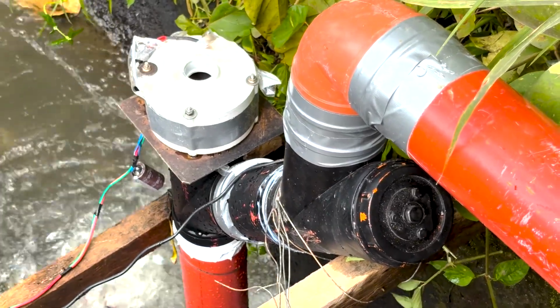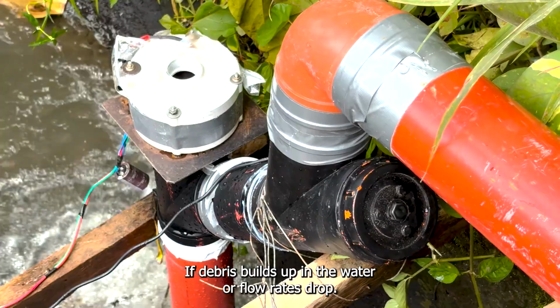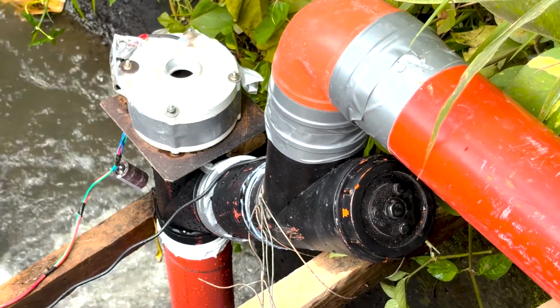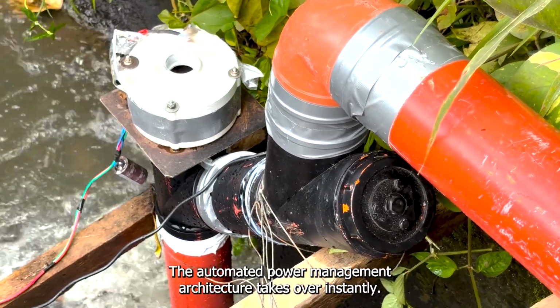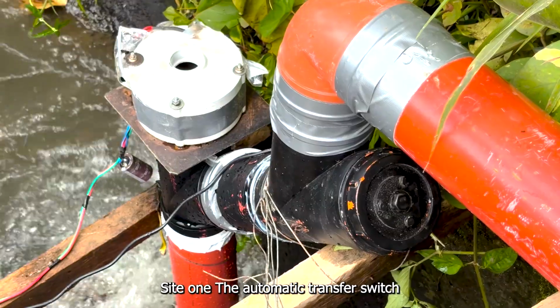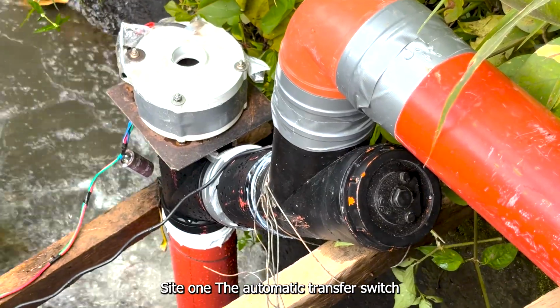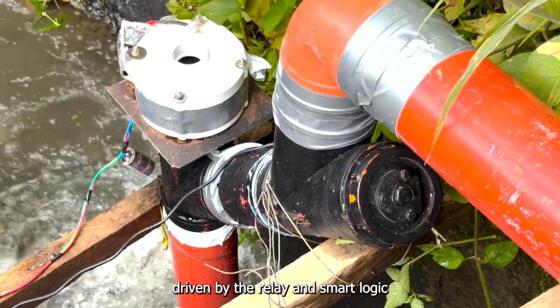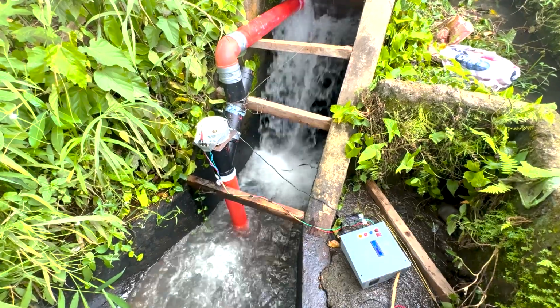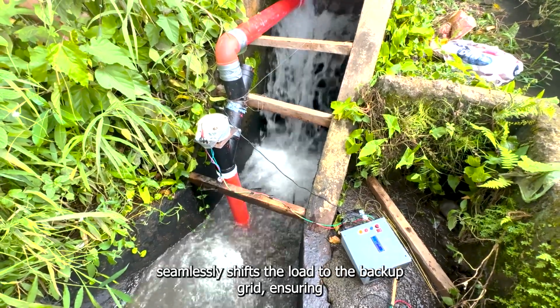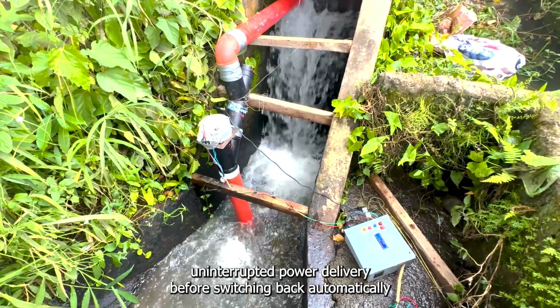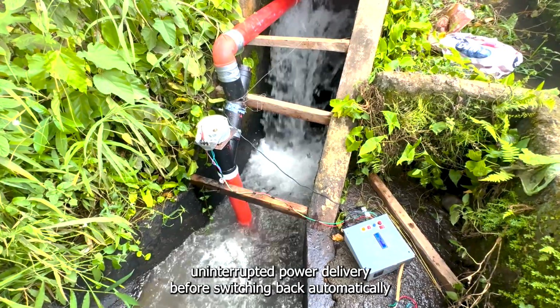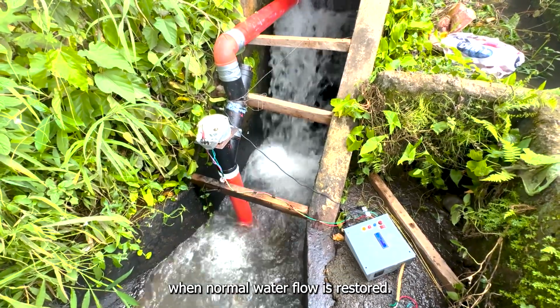If debris builds up in the water or flow rates drop, the automated power management architecture takes over instantly. The automatic transfer switch, driven by the DP/DT relay and smart logic, seamlessly shifts the load to the backup grid, ensuring uninterrupted power delivery before switching back automatically when normal water flow is restored.